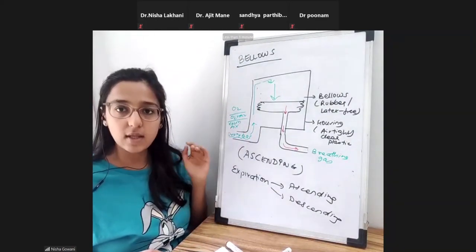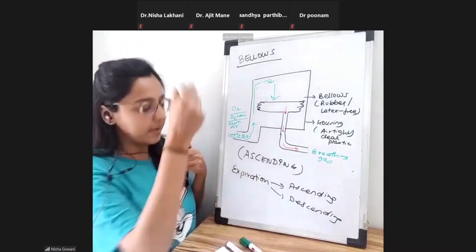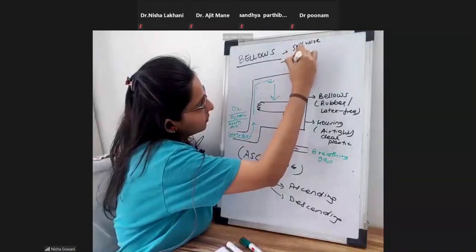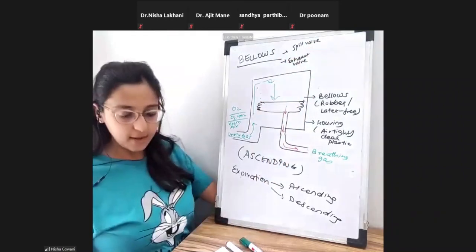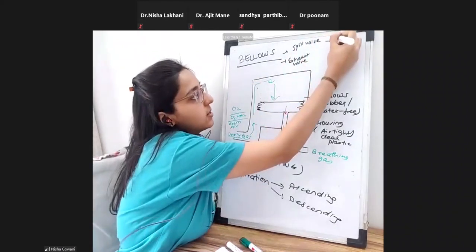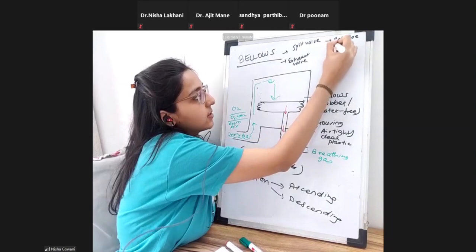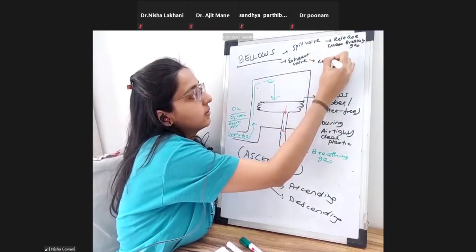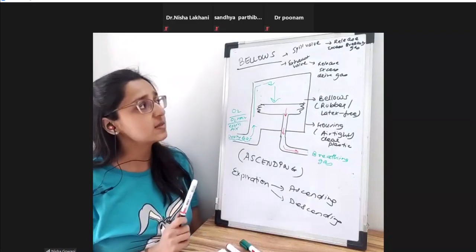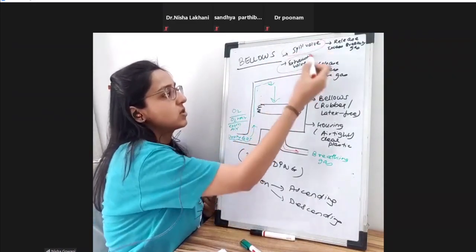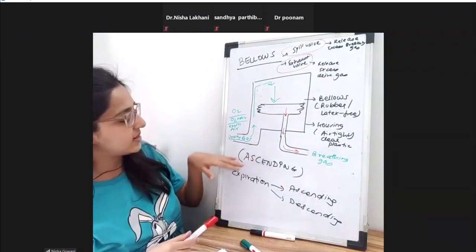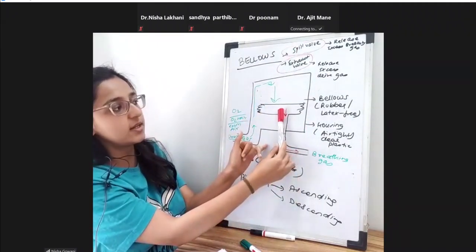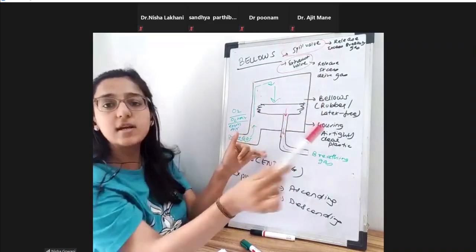There are two valves in a bellows assembly. There is a spill valve and an exhaust valve. The spill valve releases excess breathing gas. The exhaust valve — if there is excessive drive gas pressure generated inside — will release the driving gas. The spill valve will release excess breathing gas if there is excess pressure generated within the bellows while filling.